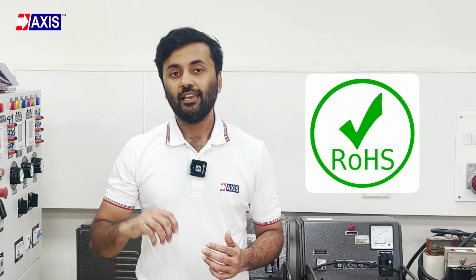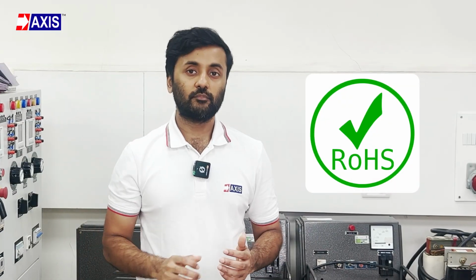It is made from bentonite and mixed with salts and minerals. This improves conductivity and helps the compound perform better in loose, shifting soils. The compound is odorless and non-leaching, which means it does not release harmful substances into the soil. This makes it safe for the environment and for long-term use. Axifill-lite is RoHS compliant, confirming it is free from hazardous materials. Its measured resistivity is less than or equal to 2 ohm meters, which is suitable for most grounding applications.